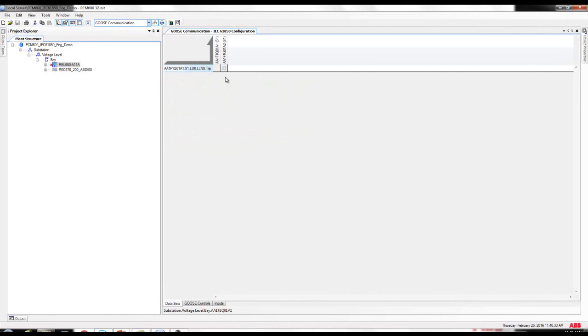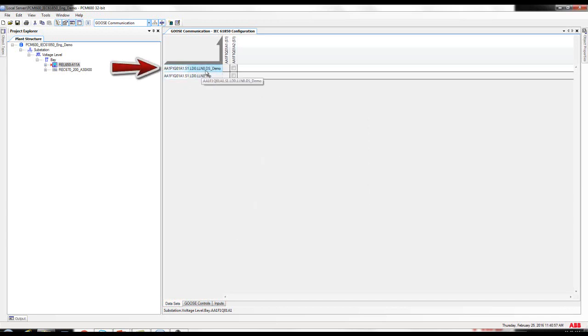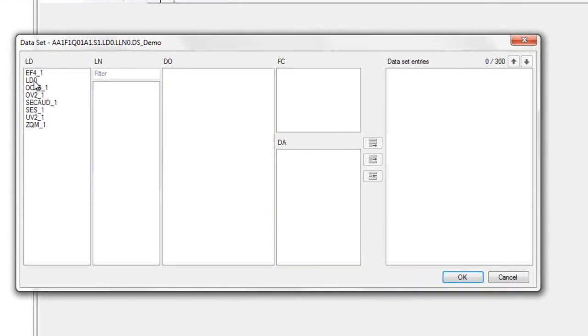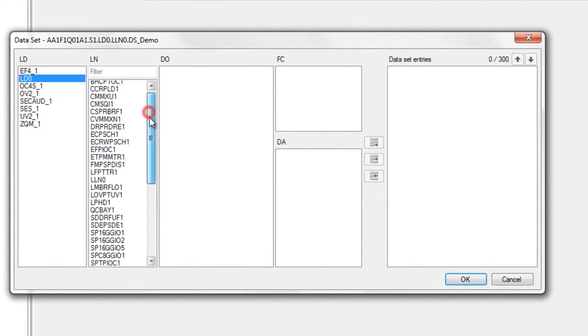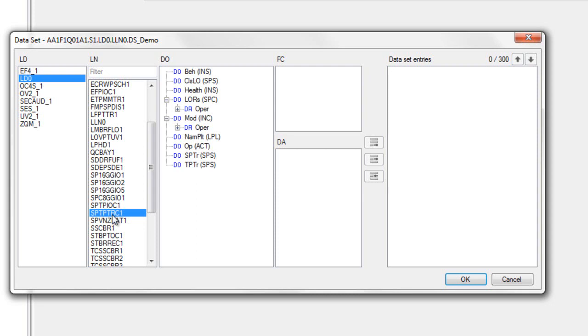The REL650 contains some datasets and GOOSE control blocks by default. What we are going to do here is add one dataset — right-click, new, and type the name of the dataset. Click OK, and now double-click on the dataset and add the information that we need from the REL650 relay. The SPTPTRC1 logical node is contained on the LD0 logical device. Click on the LD0 logical device, scroll down, and click on SPTPTRC1. Once you click on it, we look for the operation, because that is what we want to publish. We can filter here by status.